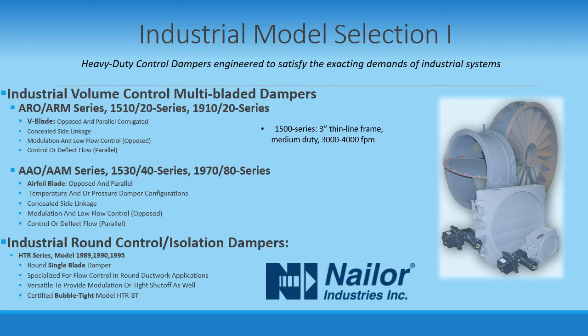Opposed blade action means that each adjacent blade moves in an opposite direction from the blade next to it, allowing for modulation of airflow as well as on-off operation. This allows for greater control and adjustment over the volume of airflow through the entire operating range. Common applications are fan discharge, power generation, air filtration, and process control. Lower leakage is attainable with opposed blade orientations since the blades overlap when closed and more torque is applied to the blades when closed as well.